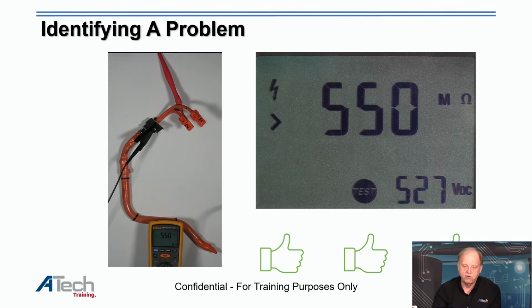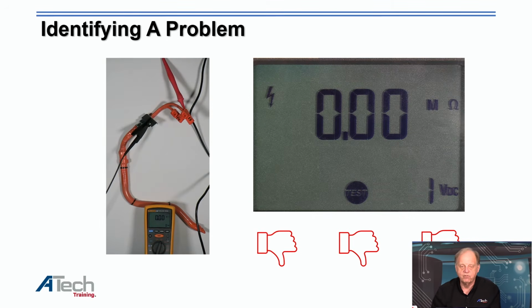If I go to my next slide, you'll notice this one would tell you that we have a problem. It has to be over 550 megohms - if I'm not there, we have an issue. The other thing at the bottom shows 1 volt, so immediately it knows we have a problem, and the circuit is telling you that you need to fix this and be careful while testing.